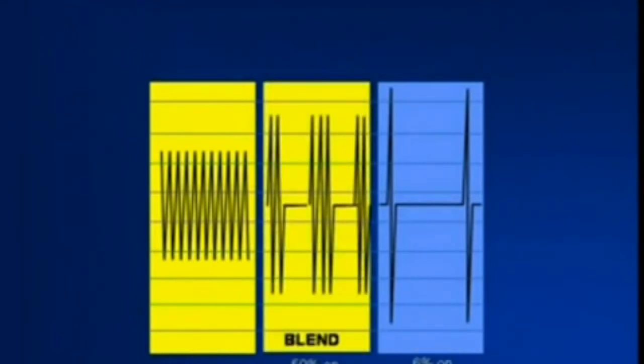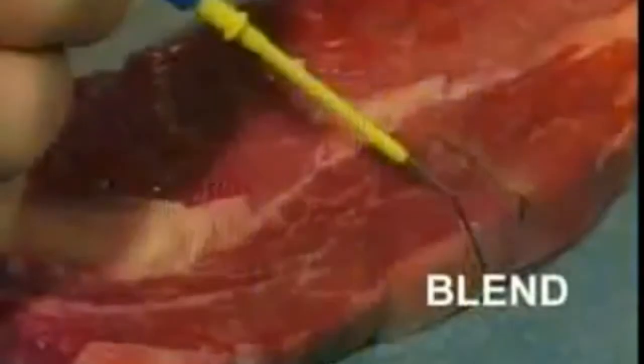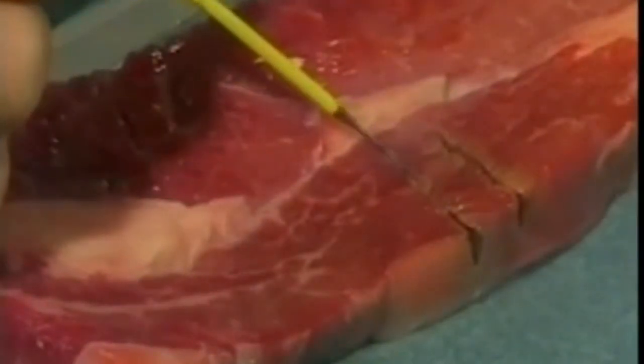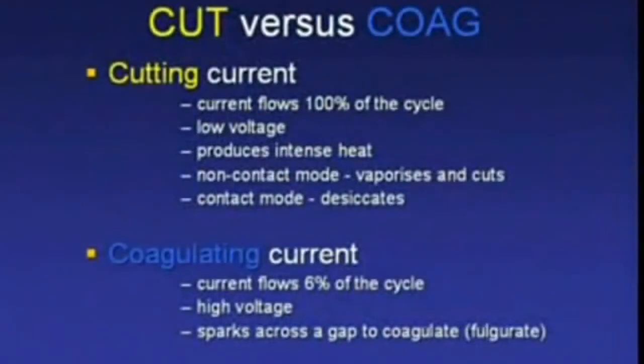Blend sits somewhere between these two modalities, where the peak voltage is higher than cut at over 3000 volts, but lower than coagulation, and the power is on and off for equal amounts of time. Blend provides cutting with hemostasis. Here we have summarized the properties of cut and coagulation. Note the differences between the duty cycle, the peak voltages, and the effects that each of these modalities achieve.